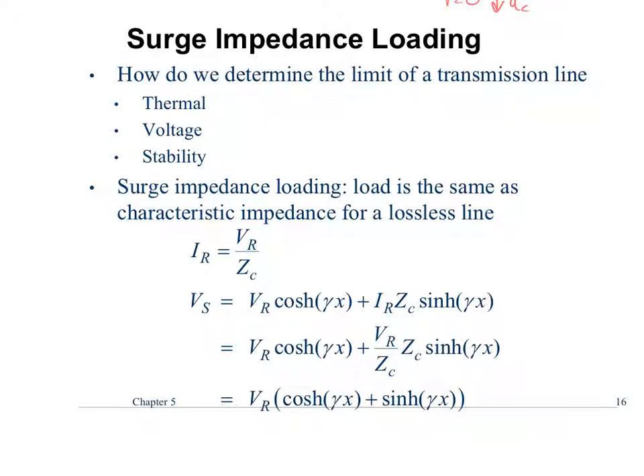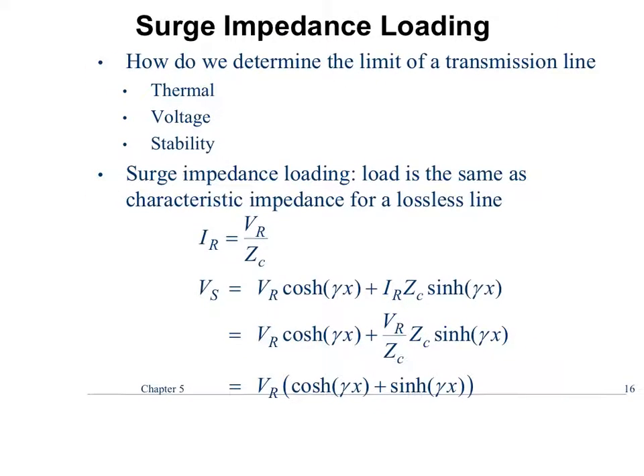So a transmission line has a lot of stuff that needs to be analyzed or looked at, but there's three key things in terms of operation. Not even talking about faults at all. This is under normal operating conditions. We have thermal limits, voltage limits, and stability limits, and the longer the line, each of those shifts. So when we talk about thermal, we talk about heat, right? I squared R essentially, and there are limits. Do you all remember what this means?